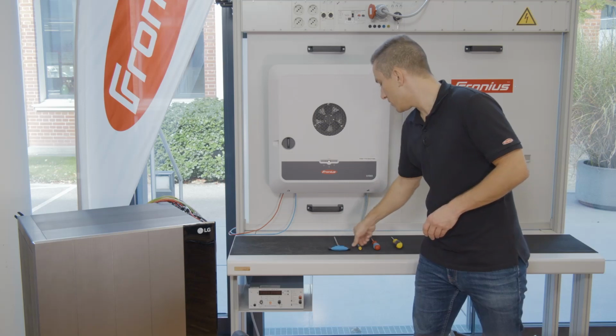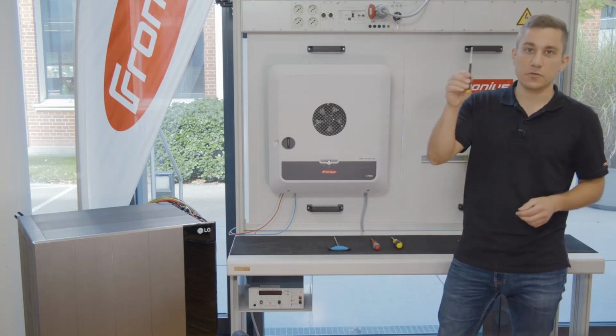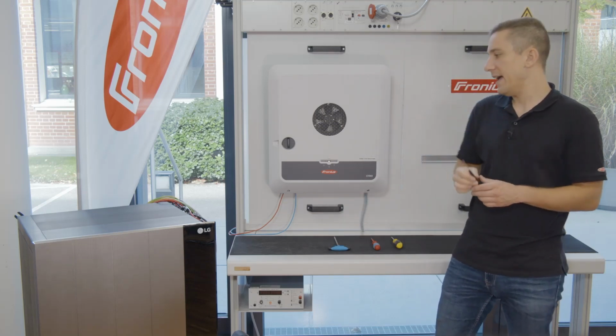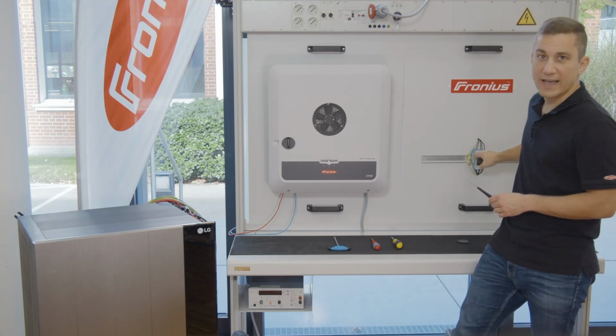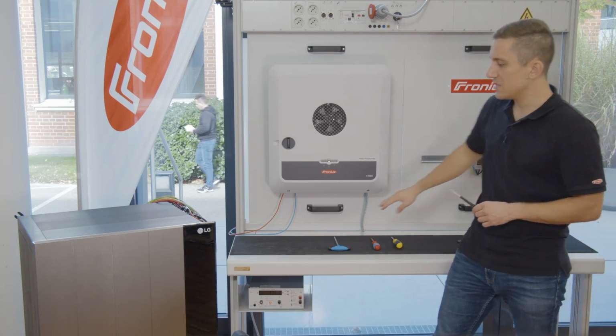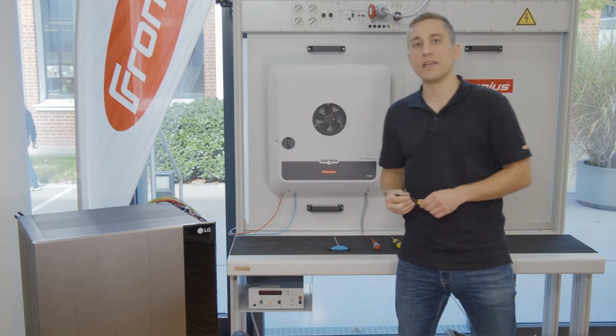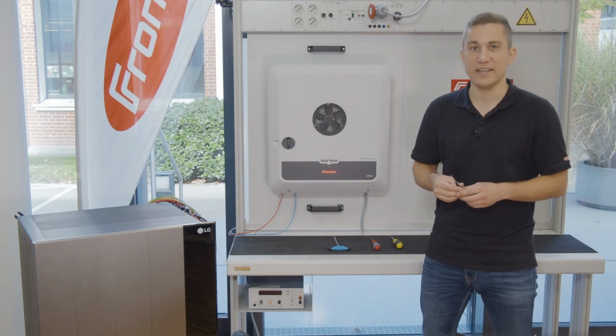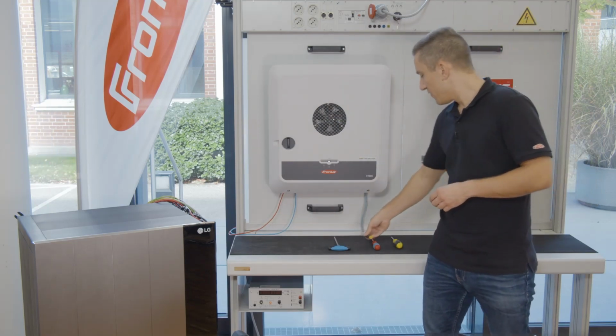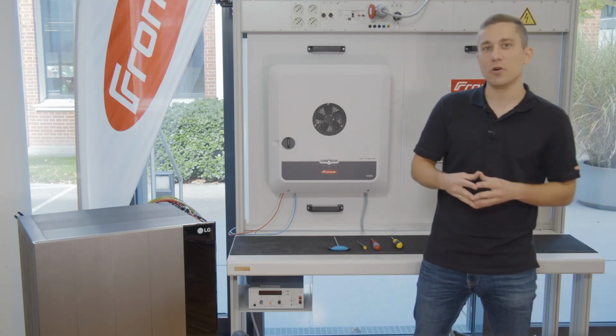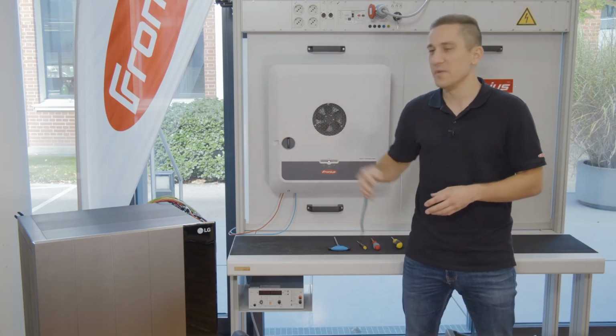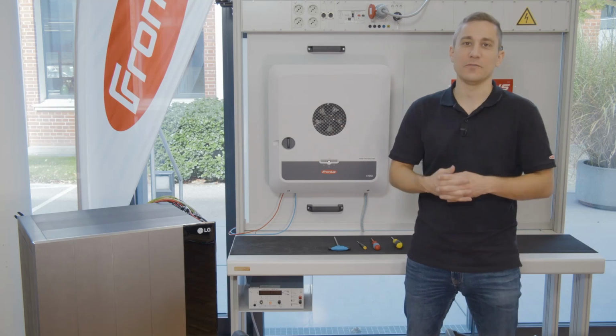And furthermore, it is always good to have a flathead screwdriver, and with that you can install the neutral conductors on the Fronius smart meter, as well as the data communication ports on the LG RESU FLEX system. So for the first part, let's start with the commissioning process, and there we are going to show you how to commission the battery system and the GEN24 Plus.